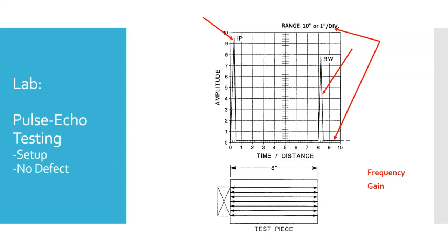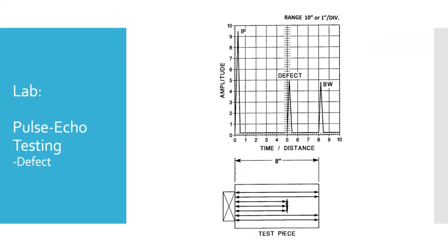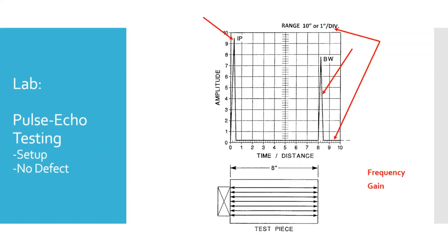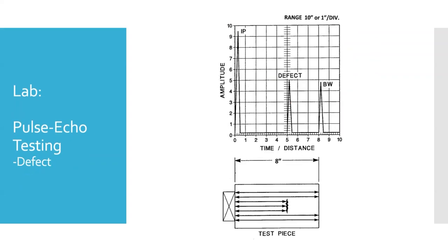You can see here in the unflawed area, we get a back wall peak that has an amplitude of about 8 on the scale, and that's an arbitrary scale. It doesn't mean anything other than they've divided the screen into 10 units top to bottom. So the back wall echo is almost 8. When we get a defect, you're still getting a back wall echo in the same spot, but it's gone lower. They show 1, 2, 3, 4, 5, 6, 7 sound lines. Here, all 7 of them are creating that back wall echo. Here, 4 of them are still creating the back wall echo, and 3 of them are bouncing off this crack that's at about 5 inches.